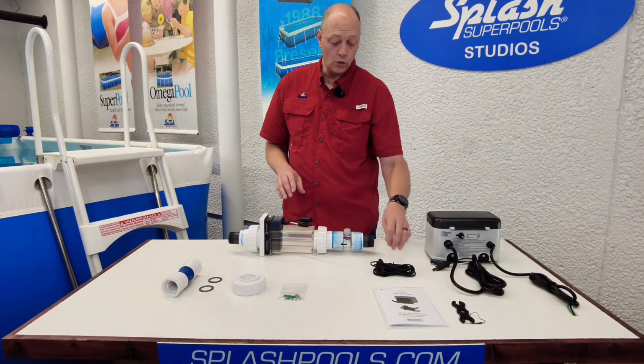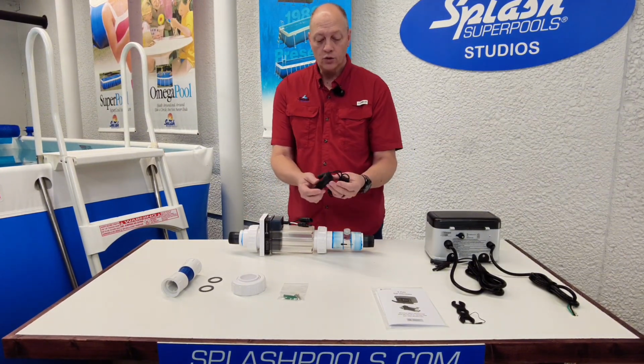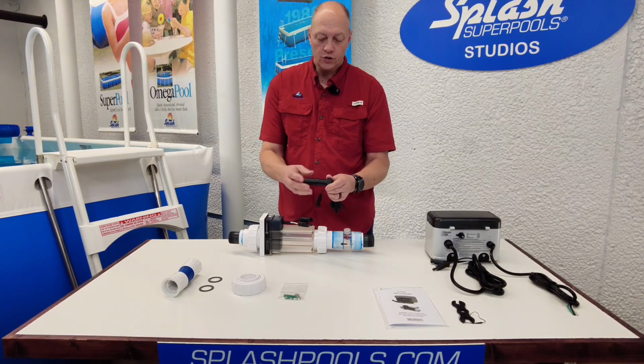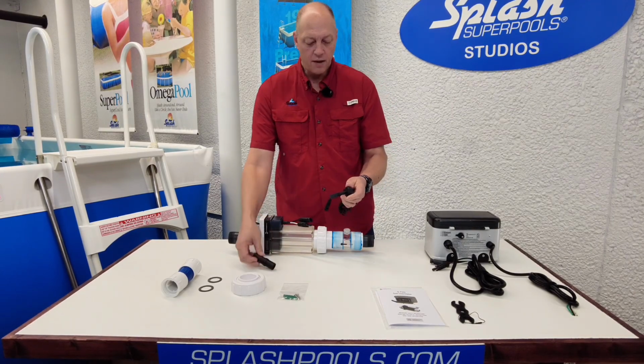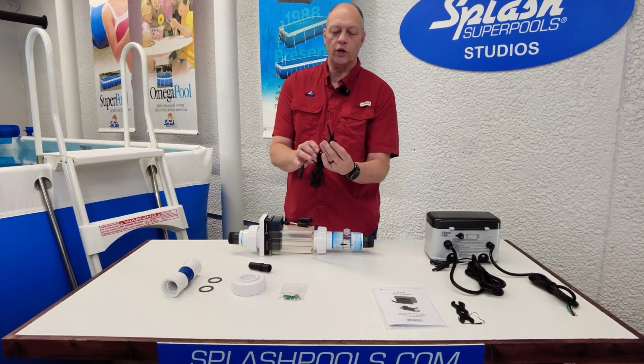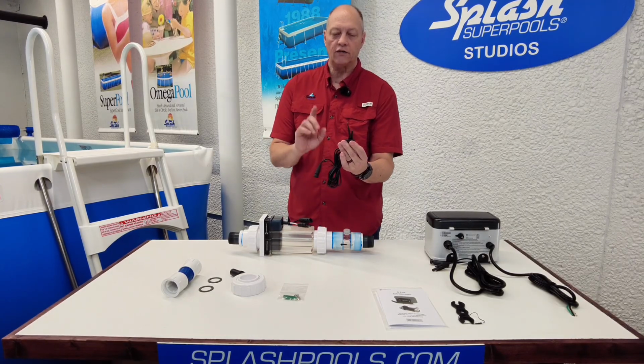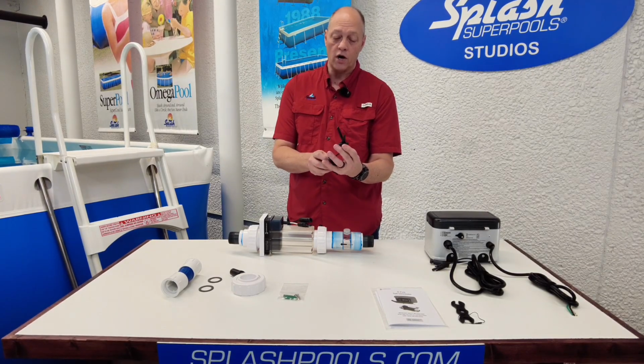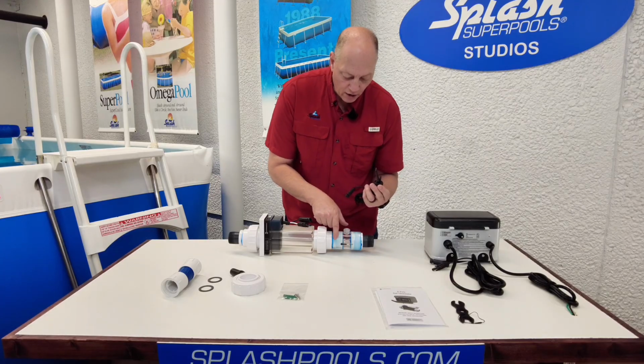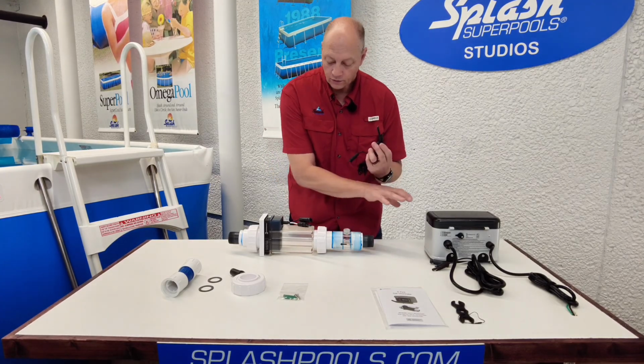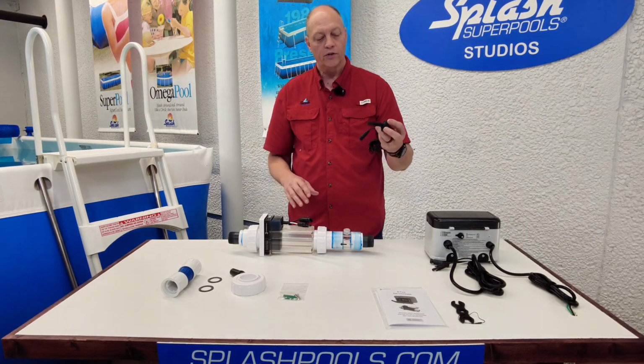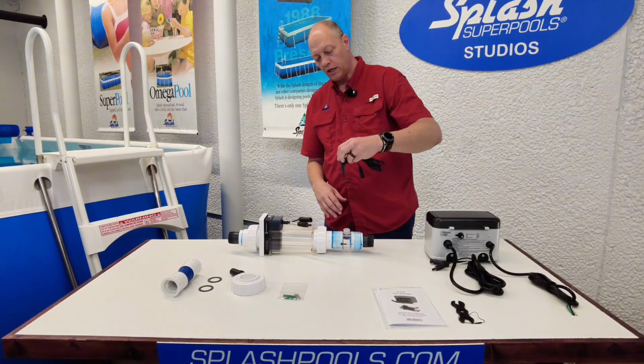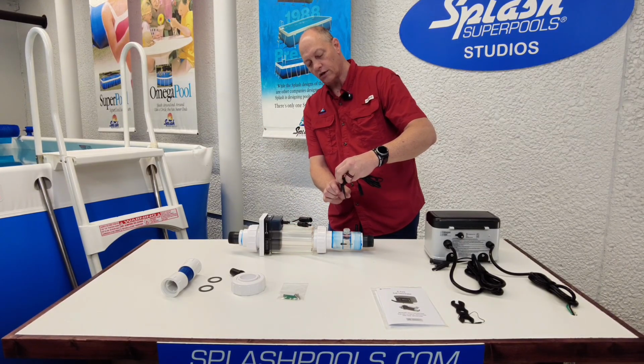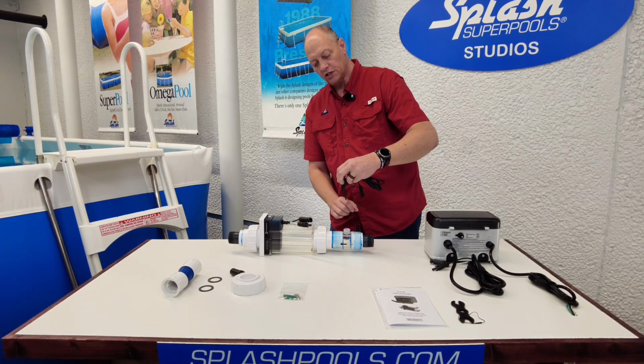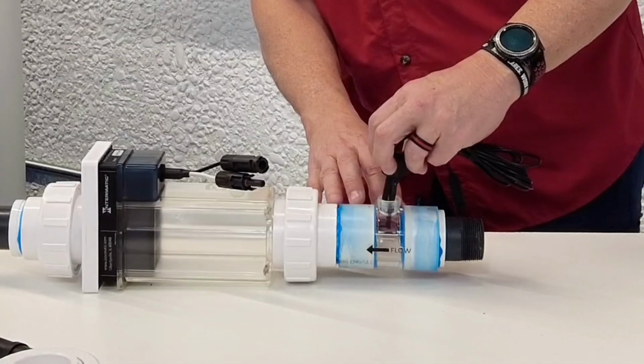Now we're going to put the flow switch in. So this is your flow switch. We're going to unscrew this cap, and you'll see on the flow switch that it has a paddle and a stick. These are important because they have to be going in the right direction. You'll notice the arrow on the flow channel - water is flowing through this direction. So we want this flow switch to be in like this so that the paddle pushes up against that stick when the water is flowing.